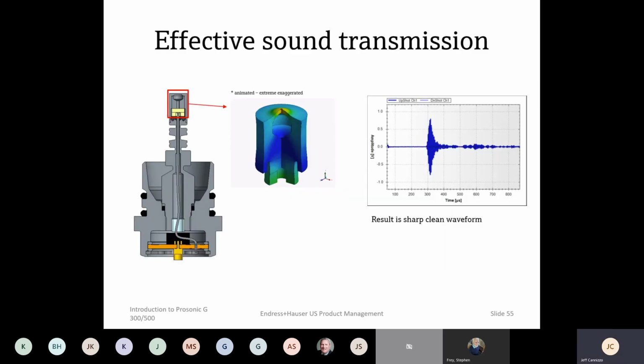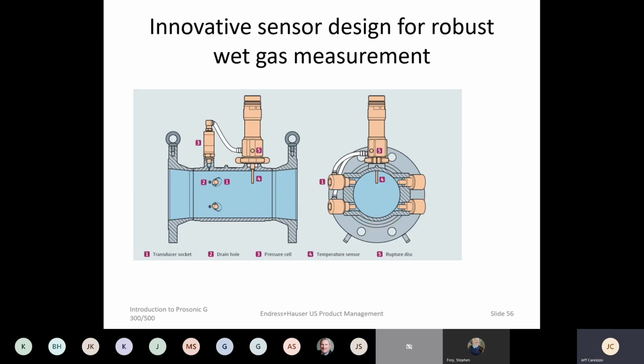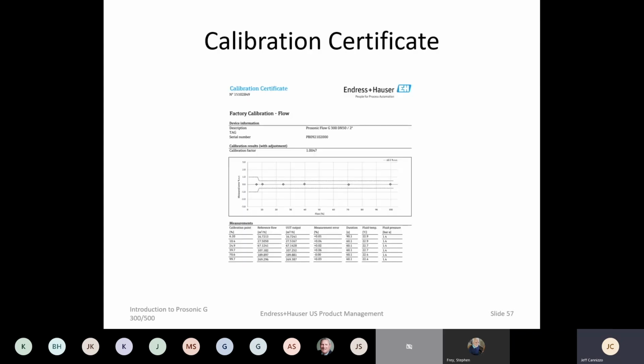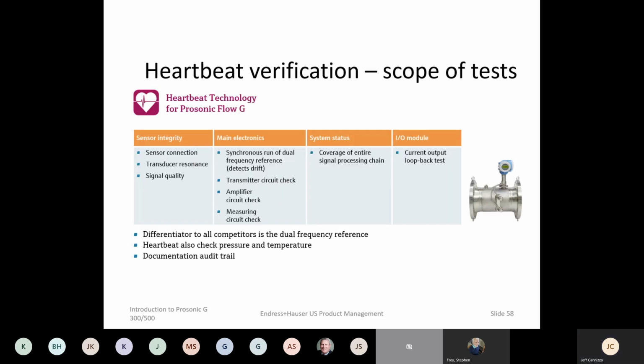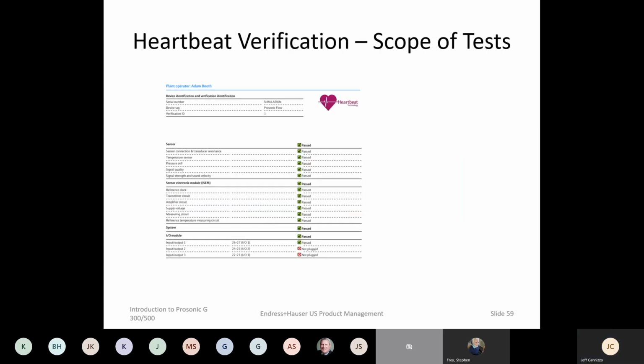This shows you a little bit about how that sound transmission works and what the inside of the meter actually looks like, with the transducers and pressure and temperature sensors. And of course, it comes with a calibration certificate, like I mentioned. And a little bit on the heartbeat technology: it does check all the sensors, not just the transit time. It will check the pressure and temperature as well, and output any type of alarms that you need to know if something's going wrong. And I think that's about it, Steve.